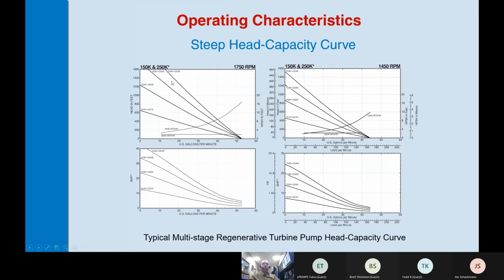To show you a curve up close, this is a 4-stage regen turbine curve. And as you add stages, it adds pressure similar to a regen turbine, but you can see it doesn't add any flow to it. So where you're only hitting 50 gallons a minute, we're hitting all the way past 1,600 feet of head. So it's a very high pressure pump for moderately low flow.